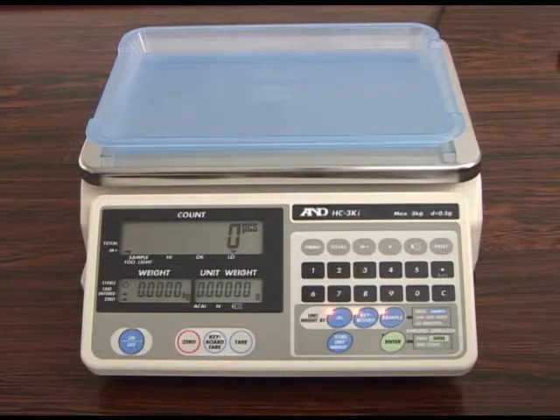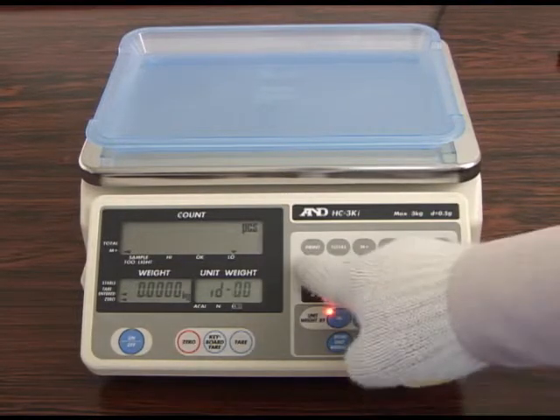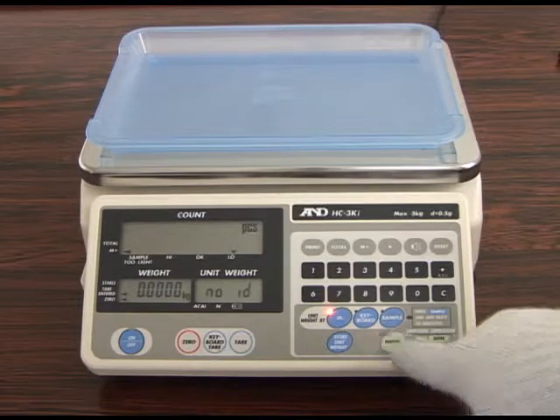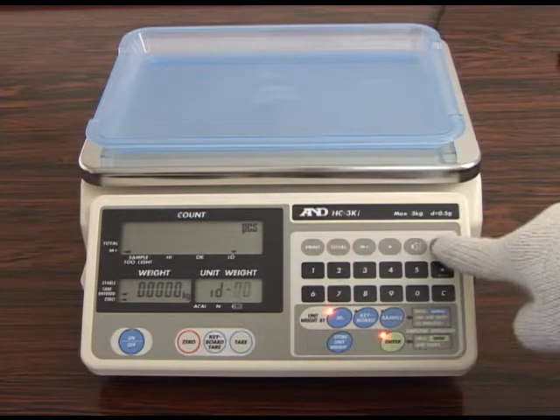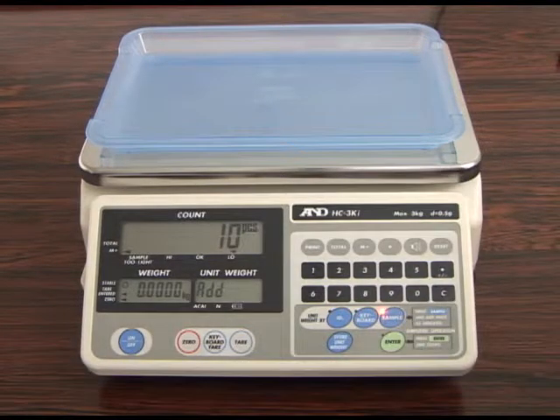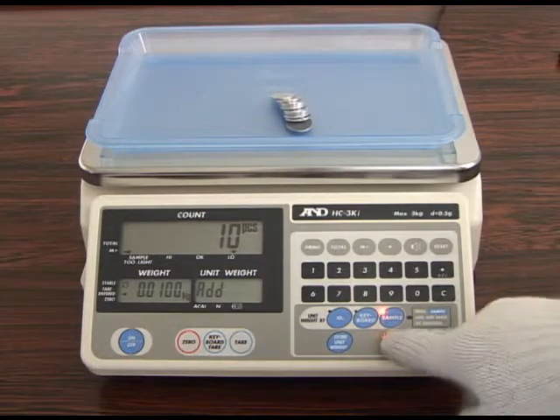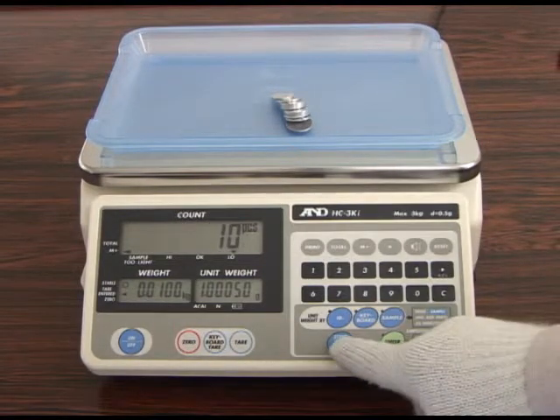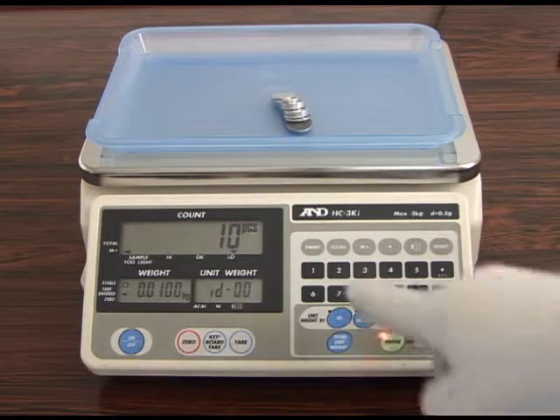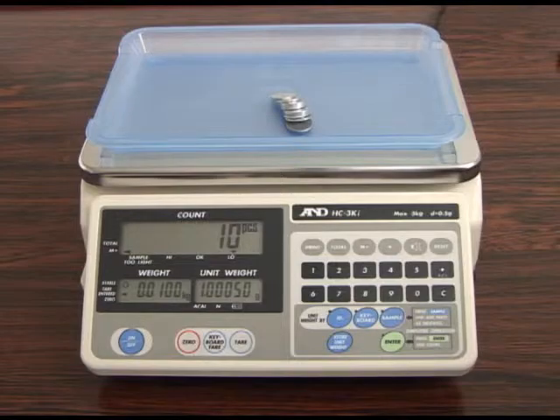The HC-i series can store data from up to 99 sample weights in its memory for simple and easy retrieval. Press the ID key, ID number and enter key to verify that there is no stored unit weight in the ID number you intend to register. Press the reset key to begin registering sample weight data. When a unit weight is shown on the display, press the store unit weight key. Select the ID number using the 10-key pad and then press the enter key to complete weighing data registration.